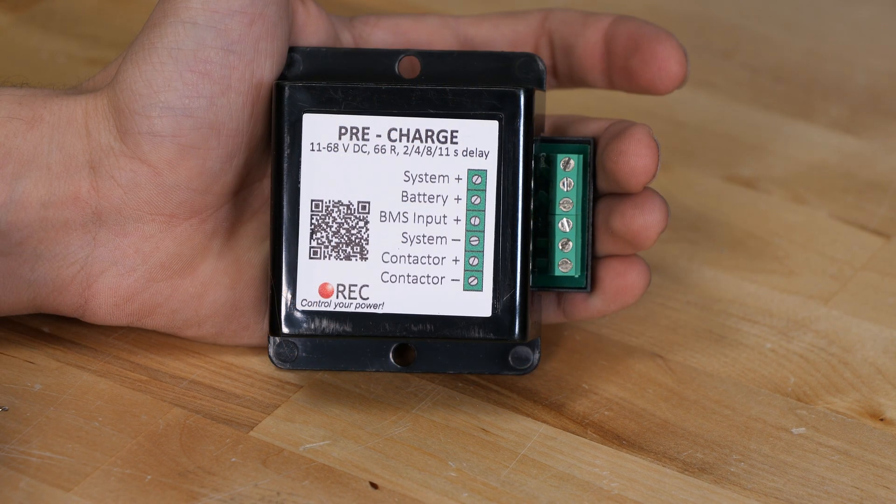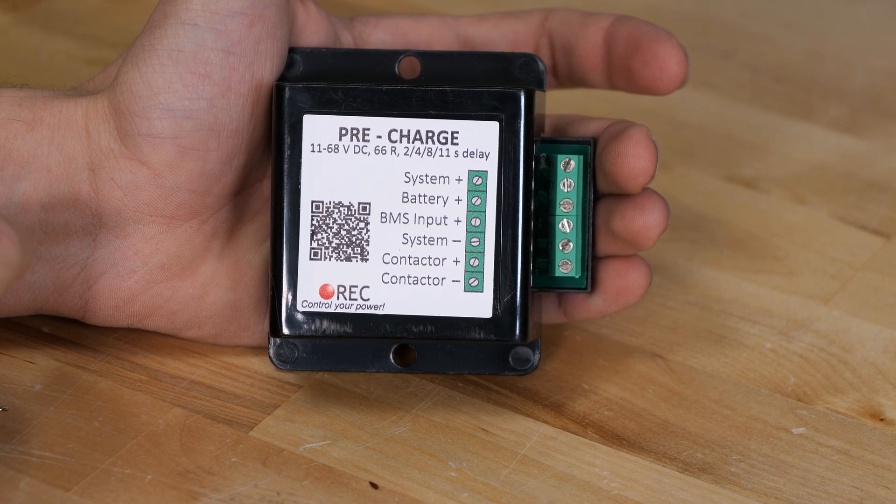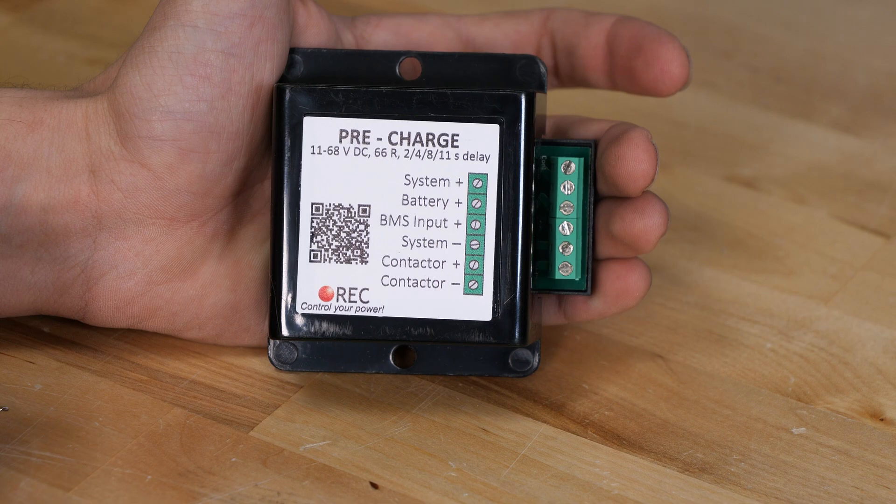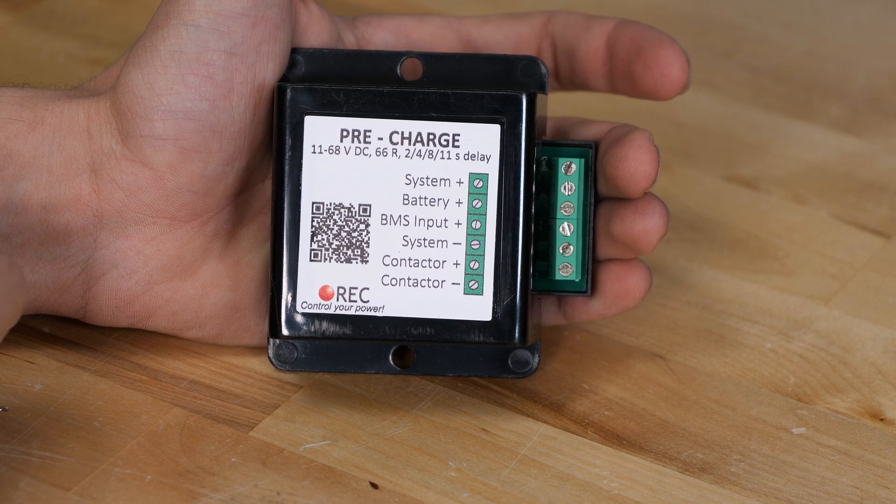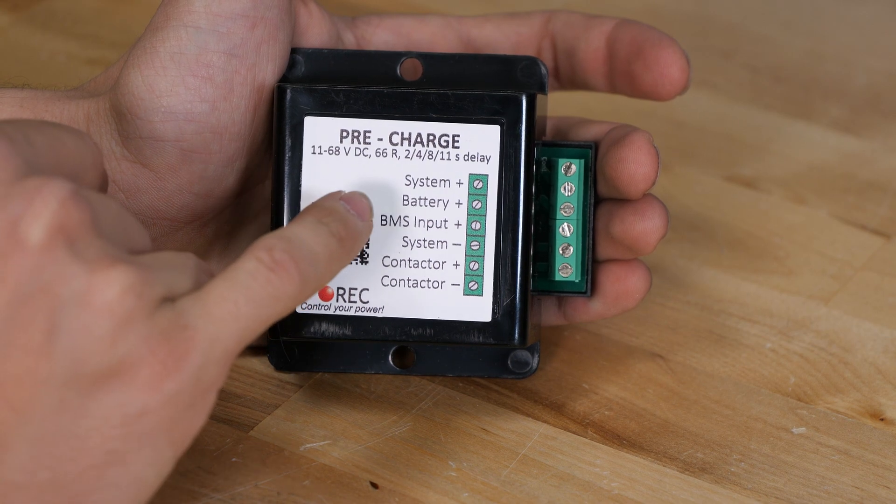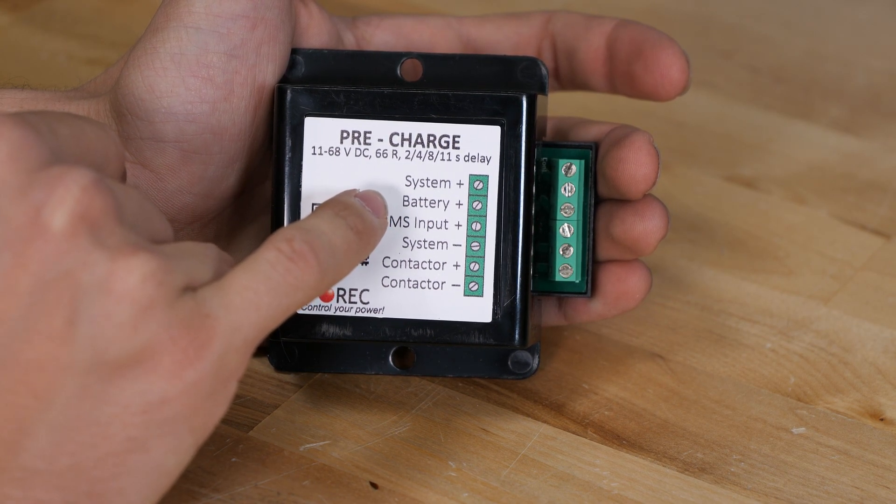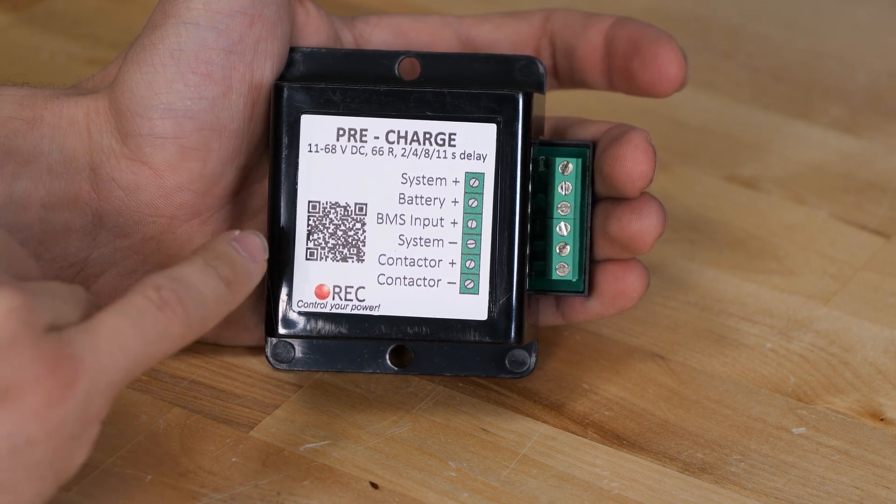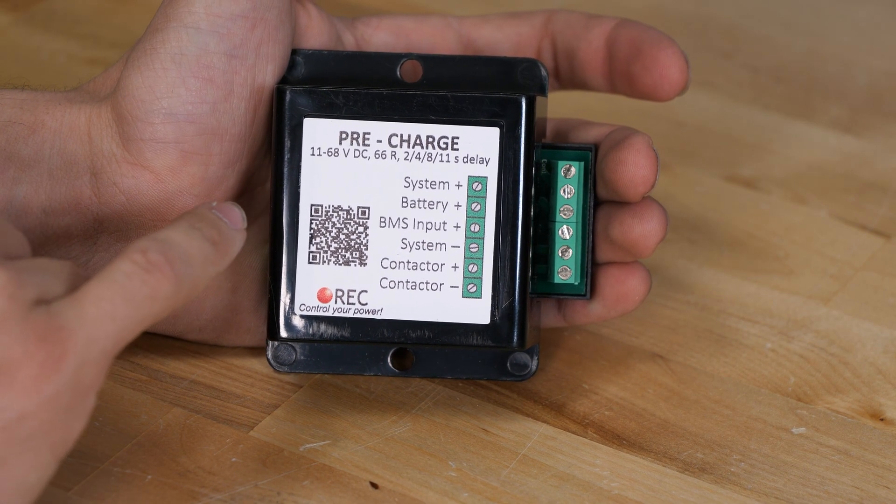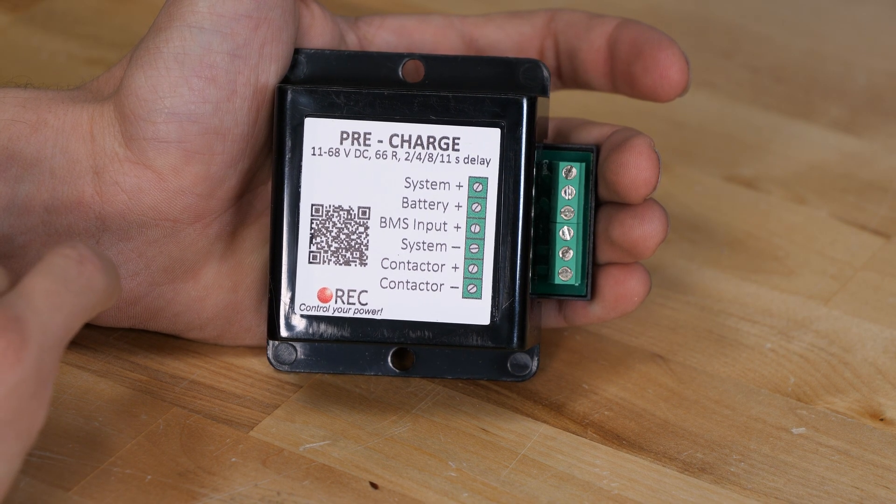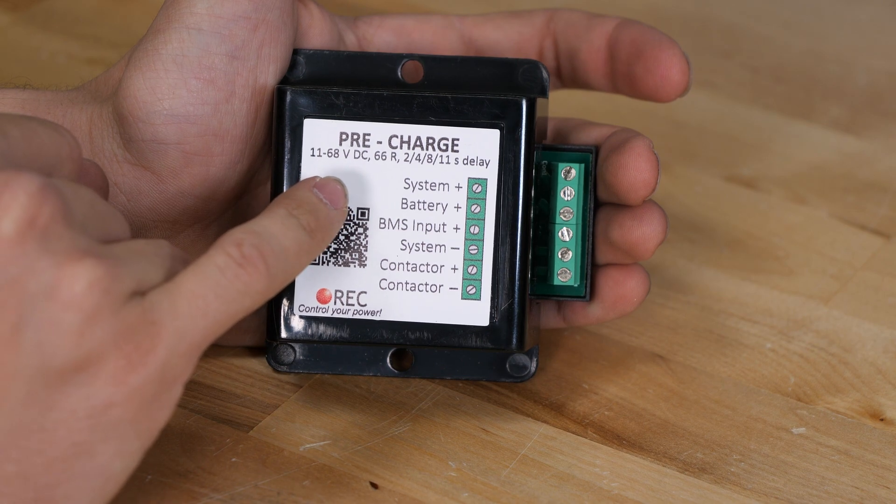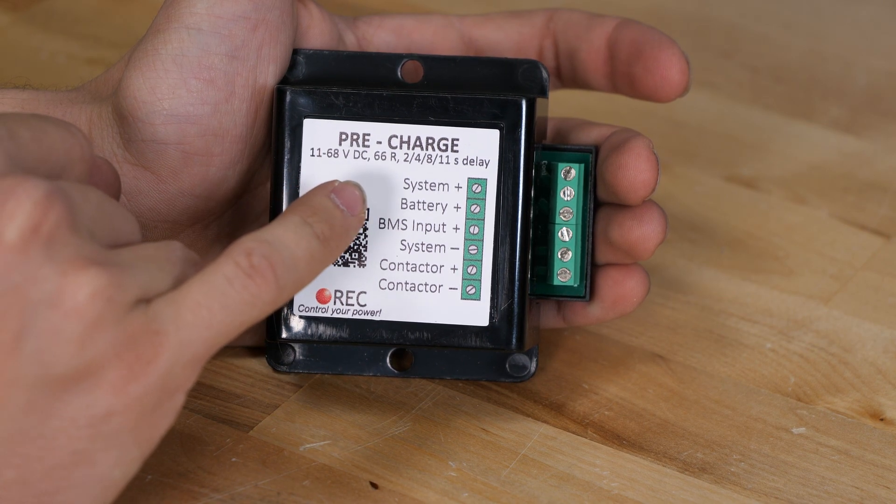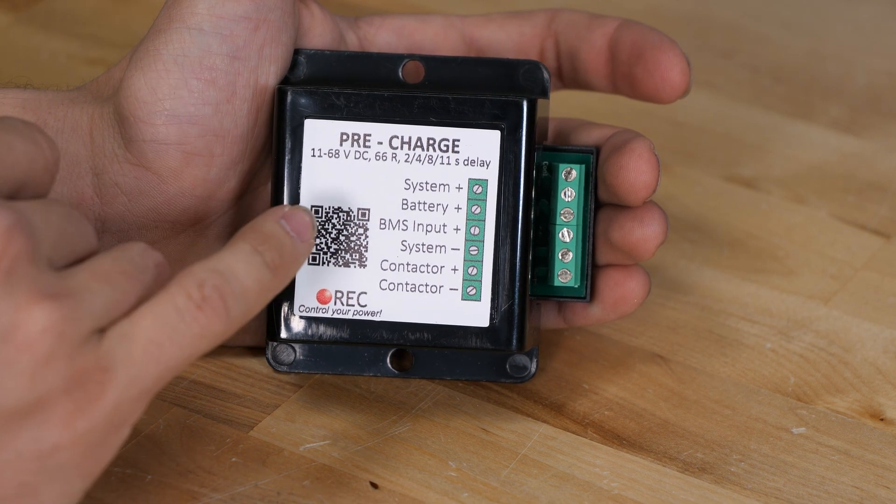This is the pre-charge delay, and this has a very important task. Essentially, when it receives a signal on the BMS input—which is the third pin down from the top—it will provide power from the system plus to the battery plus, so it essentially bypasses the contactor, but it does it through a resistor. So if you have an inverter with large capacitors, it's going to charge those capacitors up. Now this specific model is a variable delay, so it can do 2 seconds, 4 seconds, 8 seconds, or 11 seconds.